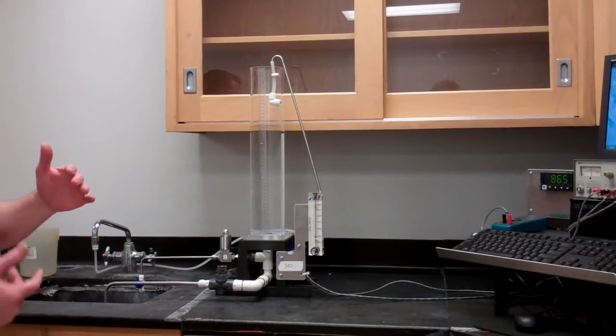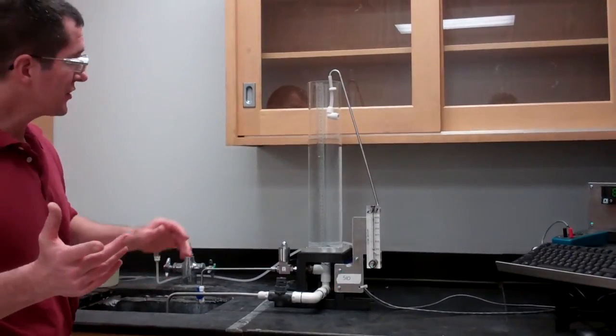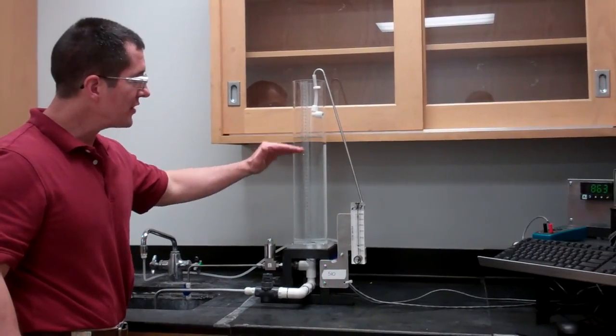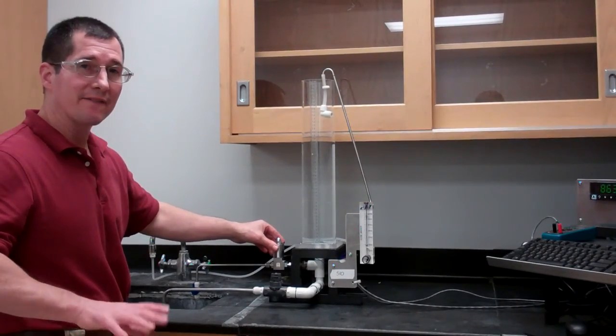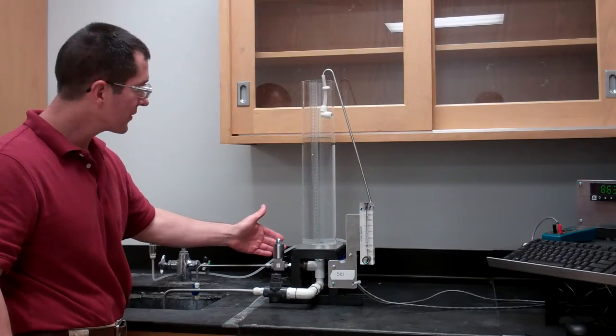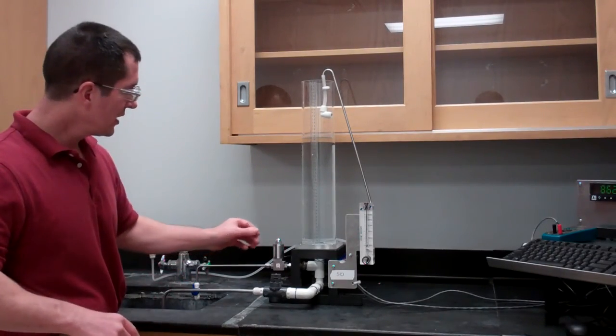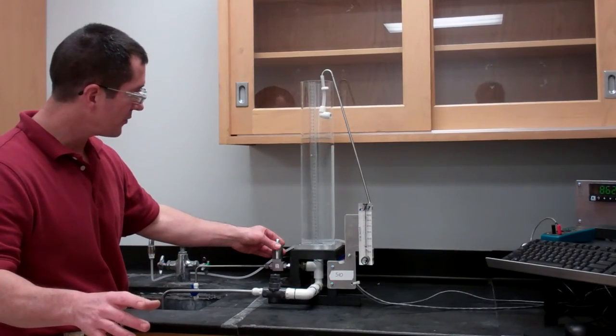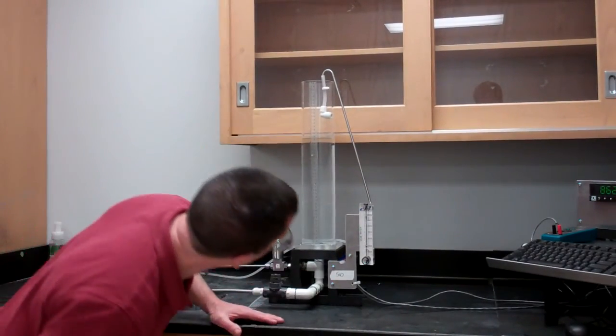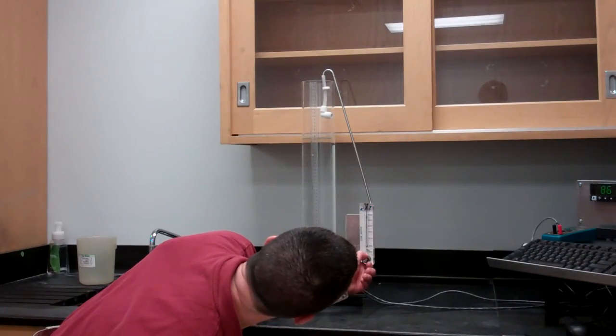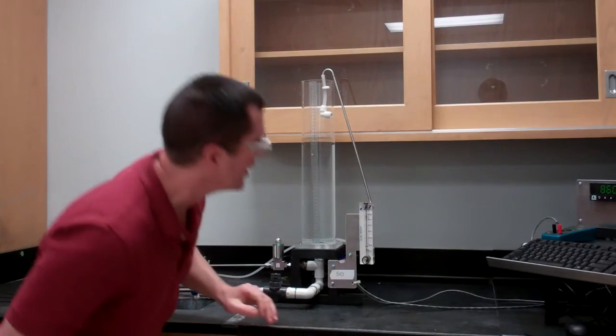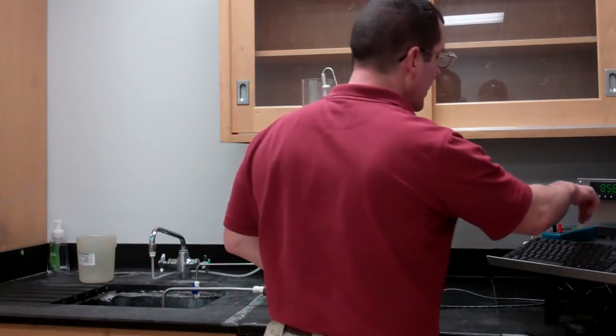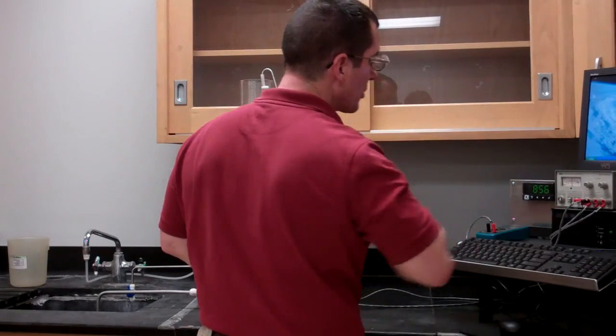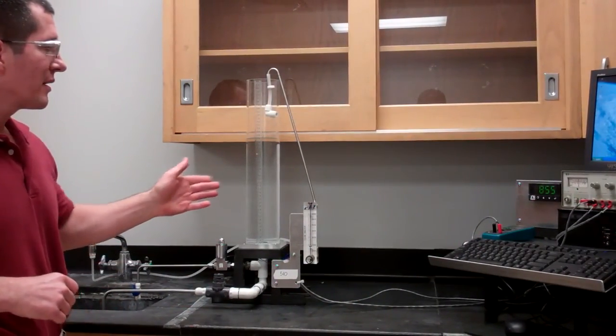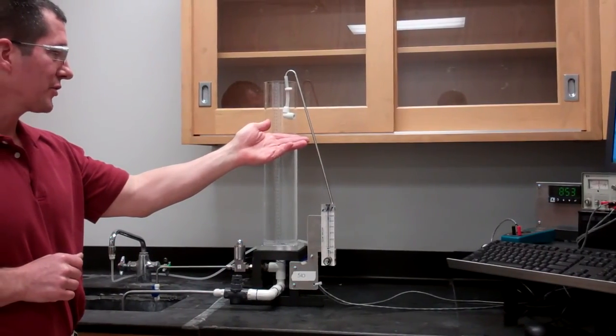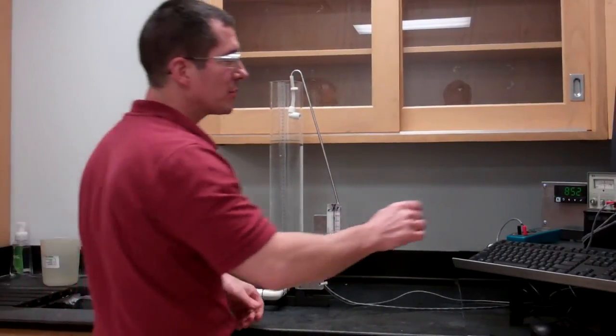Now, one of the things you're going to be interested in knowing on this system is, does the height of water in the tank influence the flow that you can get through the control valve at a fixed input signal to the valve? Let's say I set the power to one setting for the valve, and I can balance out the flow going in. Right now we've got about 550. I'm going to change it to about 500 milliliters per minute, and you can read what the input power is going to the valve. Basically what we're seeing right now is that the level is starting to drop, which means our signal may be a little bit too high, so we can back off on that a little bit.